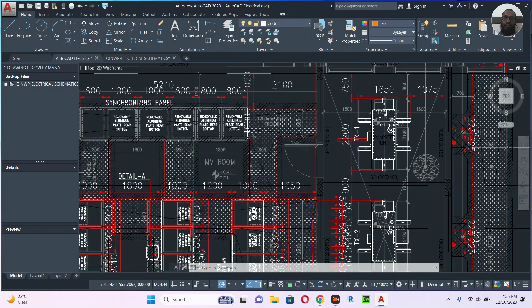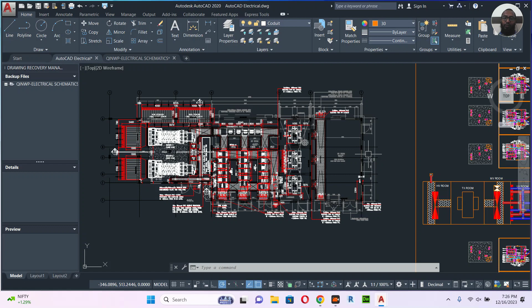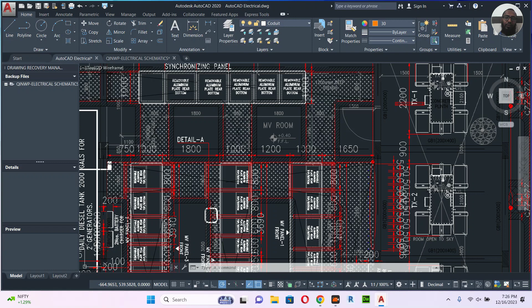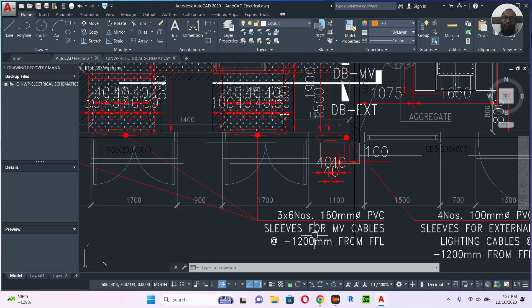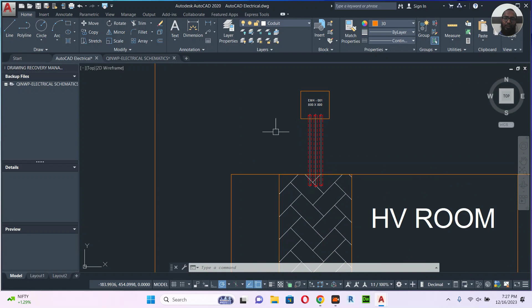I made one substation that is very deep, like a satellite project. It's very deep, and the manhole size looks like one big house. It's a very complicated drawing. So just keep in mind, this is normally 1.5 and 1.2. It can go up to 1.8, and 1.5 sometimes for the LV room. This depends. And you see all this plate, we call it checkerboard plate. These are entries. You see here 3 by 6 nos, 160 mm diameter PVC sleeves for MV cable, something like this. It depends on how many cables and how many ducts.